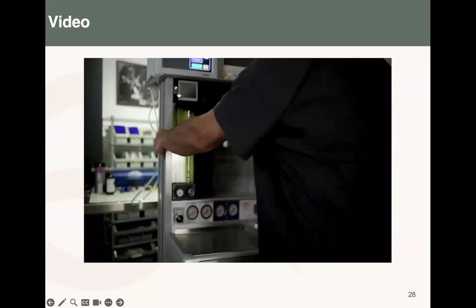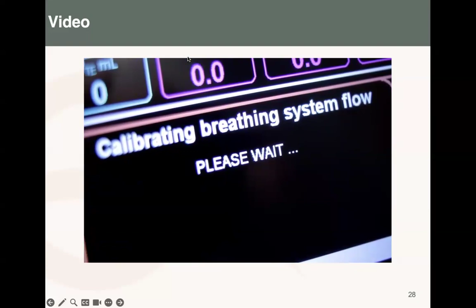Disconnect the ventilator drive hose from the ventilator and attach the red plastic adapter to the 17mm bellows driver taper on the rear of the ventilator bellows assembly. Connect the patient flow sensor with the flow in the patient direction, blue line closest to the patient, clear line closest to the ventilator, to first calibrate in the forward direction. Press the Flow Cal button. Press Calibrate Patient Flow. Press Yes to start calibration of the inspired flow. When prompted, turn the flow sensor around to calibrate the expired flow and press the Continue button. Note: the ventilator will prompt you to put the sensor in the correct orientation if it is connected incorrectly. When complete, press Exit. If the calibration fails, perform the procedure again from the beginning.